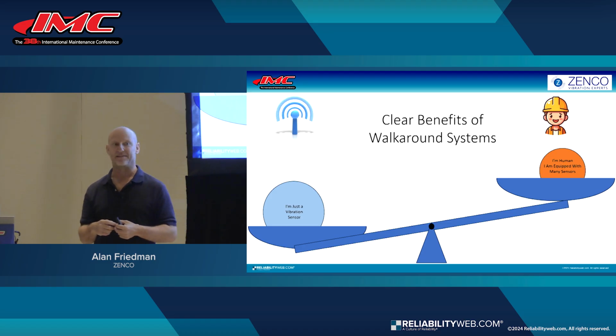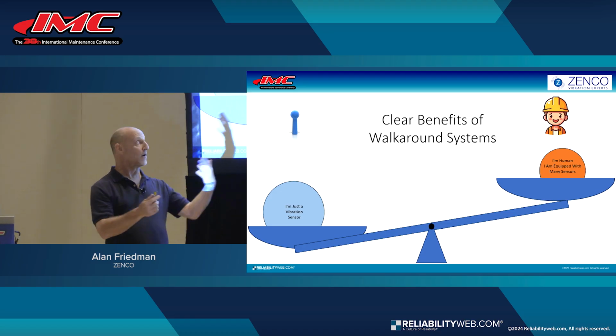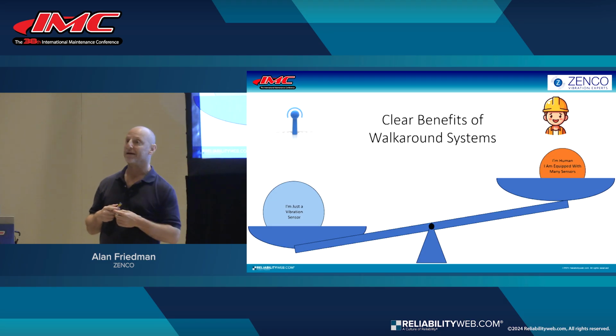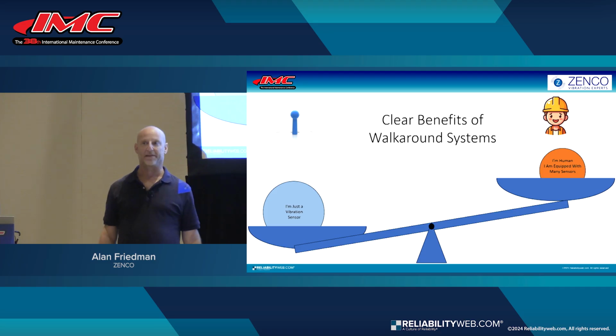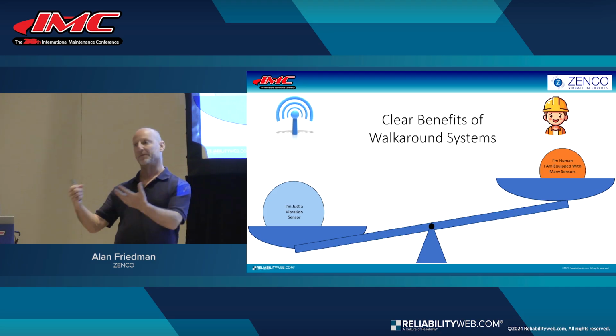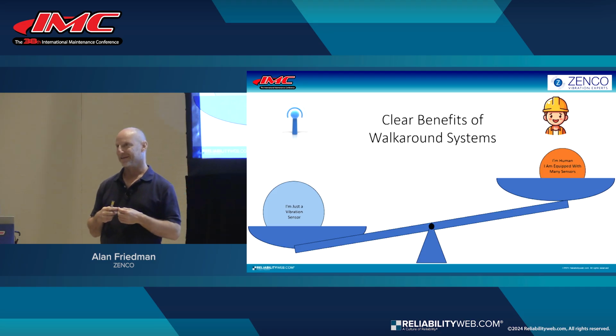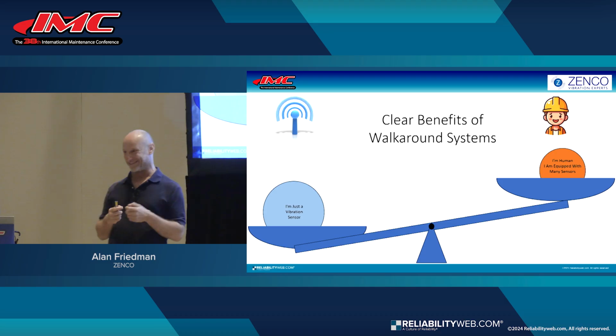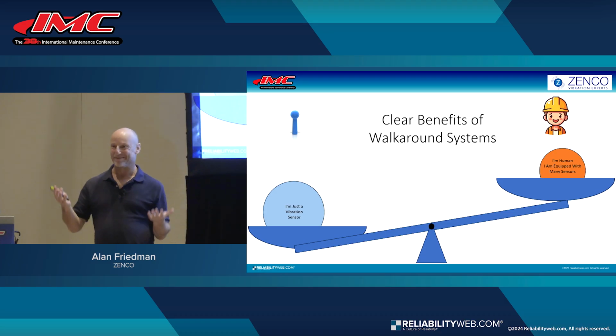So I'd say if you're going to go online, you still want to have inspection routes—someone whose job it is to walk around once a month and look for problems with the machines. But on the other hand, if you're going to pay someone to do that anyway, it's not a big deal for them to put a sensor on the machine and take a vibration reading. So it balances either way.